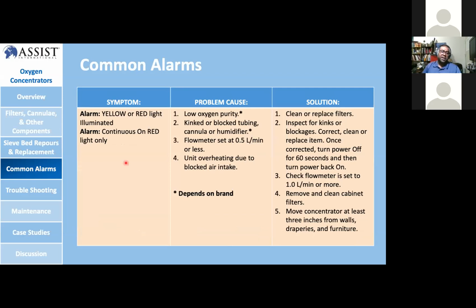Yellow or red alarm depends on the brand as well. But for most of them, it is the red alarm light, with the continuous red light on. So for purity, you get a yellow or red alarm. Kinked or blocked tubing, the cannula maybe kinked, or the humidifier is not working properly, and the flow setting is sometimes very low, so you're going to get unwanted results. These are the problems that you're going to see with this alarm.